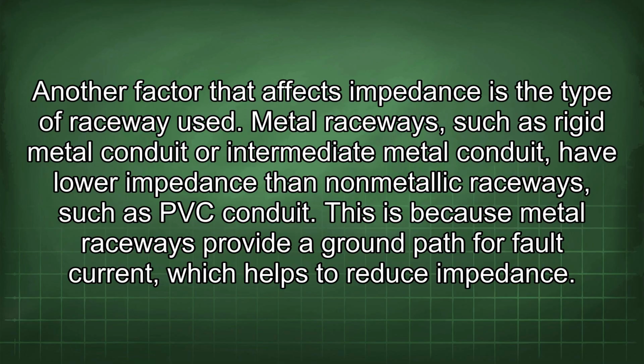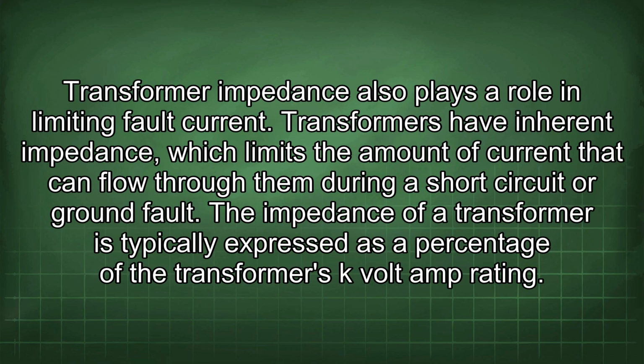Another factor that affects impedance is the type of raceway used. Metal raceways, such as rigid metal conduit or intermediate metal conduit, have lower impedance than non-metallic raceways, such as PVC conduit. This is because metal raceways provide a ground path for fault current, which helps to reduce impedance. Transformer impedance also plays a role in limiting fault current.